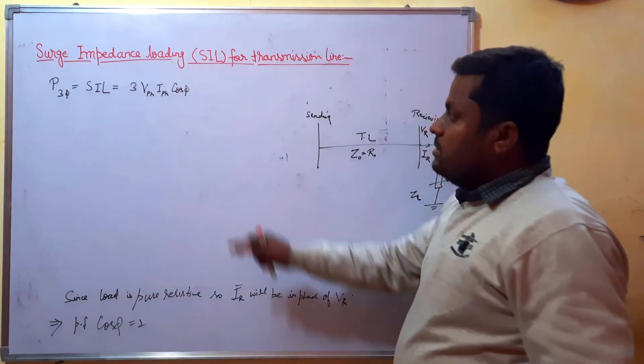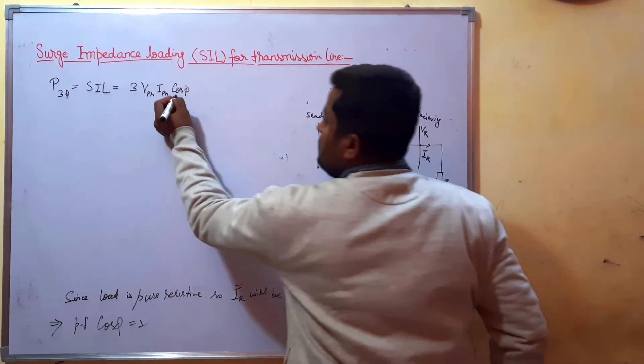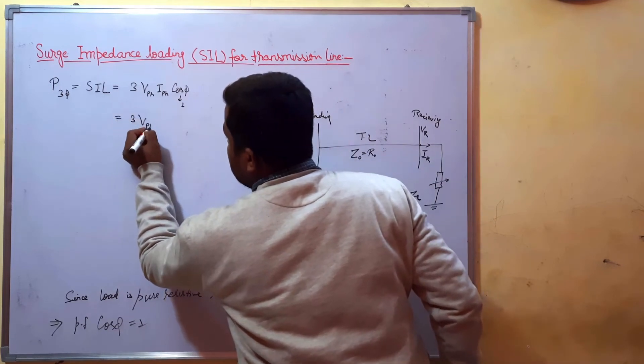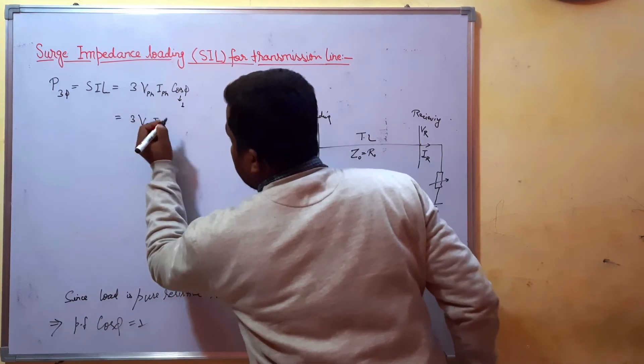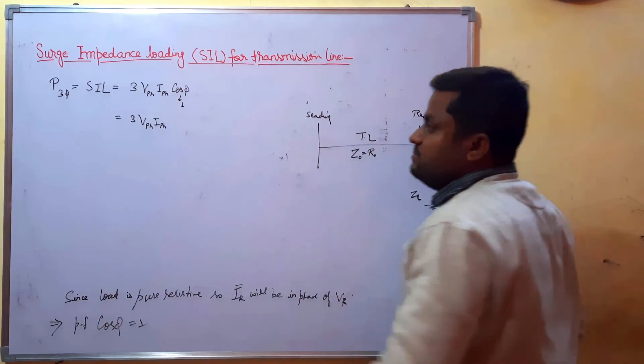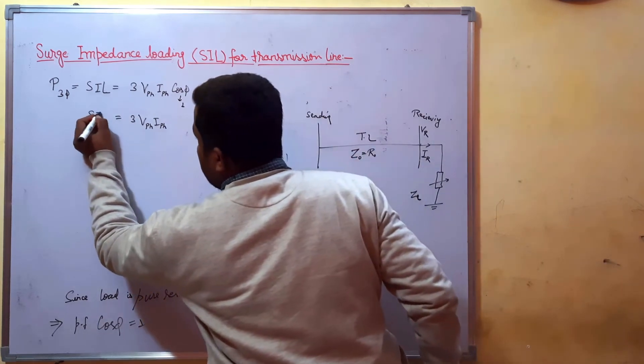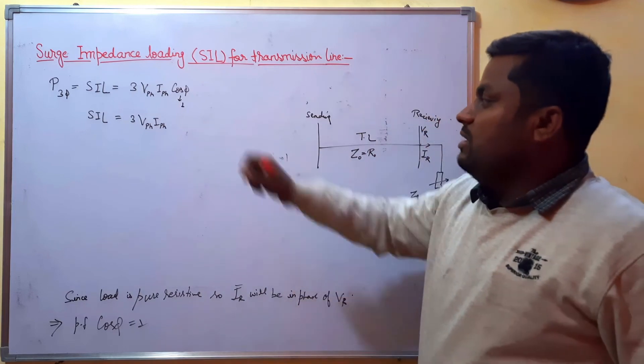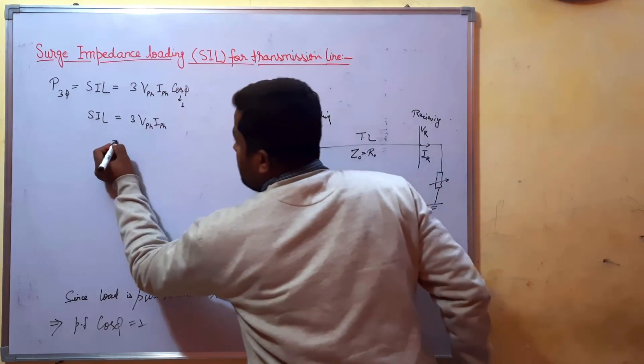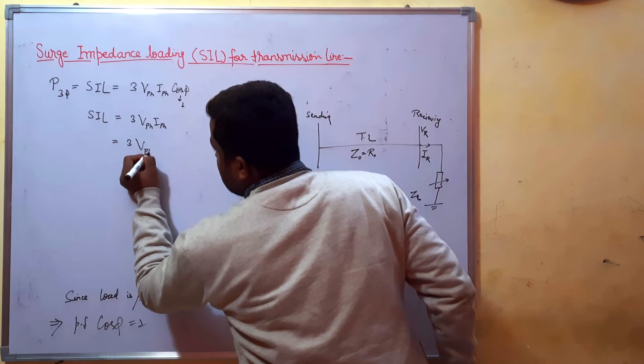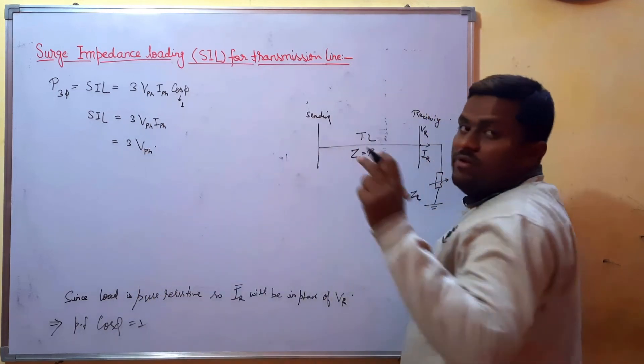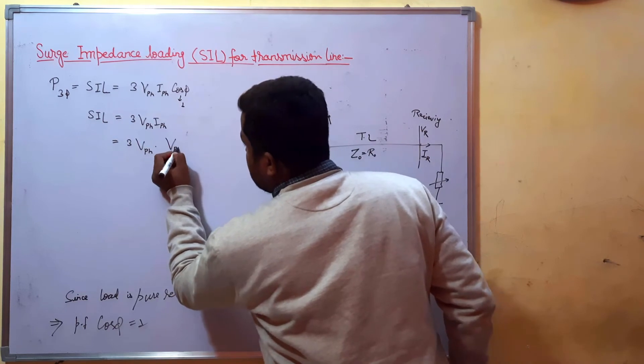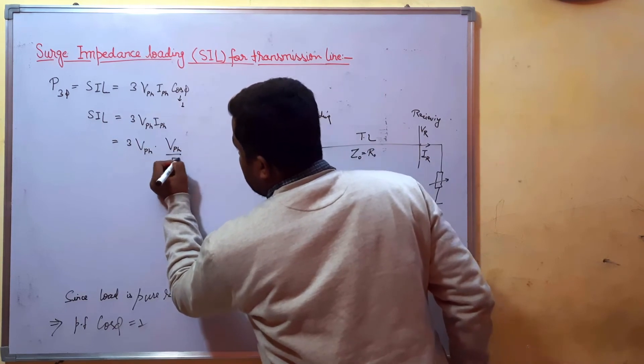The SIL equals three times Vphase times Iphase times cos φ. Since cos φ equals 1, this simplifies to SIL = 3 × Vphase × Iphase. Here Iphase can be written as Vphase / Z0.